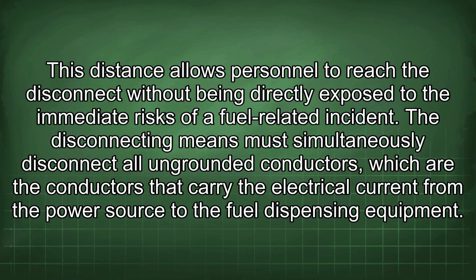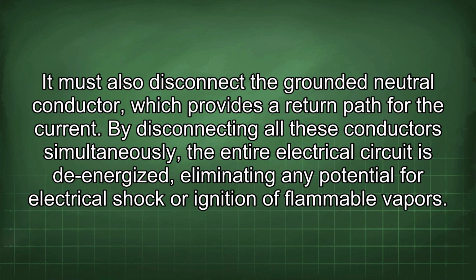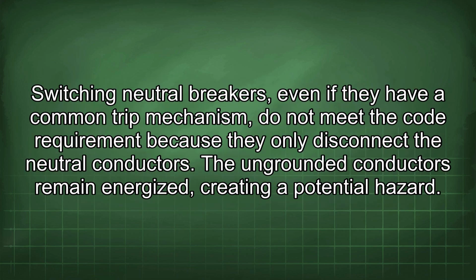The disconnecting means must simultaneously disconnect all ungrounded conductors, which are the conductors that carry the electrical current from the power source to the fuel dispensing equipment. It must also disconnect the grounded neutral conductor, which provides a return path for the current. By disconnecting all these conductors simultaneously, the entire electrical circuit is de-energized, eliminating any potential for electrical shock or ignition of flammable vapors. Switching neutral breakers, even if they have a common trip mechanism, do not meet the code requirement because they only disconnect the neutral conductors. The ungrounded conductors remain energized, creating a potential hazard.